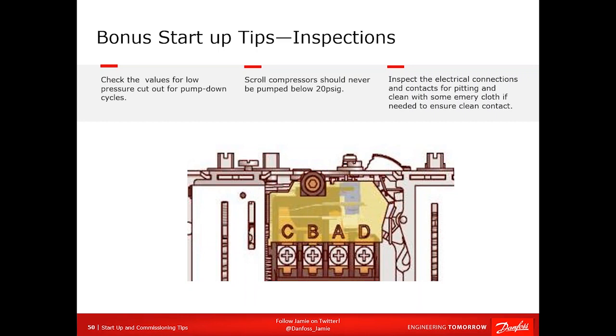No screwdriver required. Here you can see there is an opaque clear lens. Look through it, check your contacts. Make sure there's no pitting, they're not stuck together. If they are, during preventive maintenance, you can clean them with a bit of emery cloth and make sure that the unit functions with no sticking. You want clean make and break.